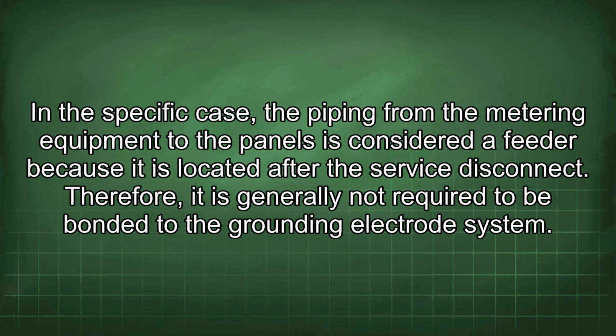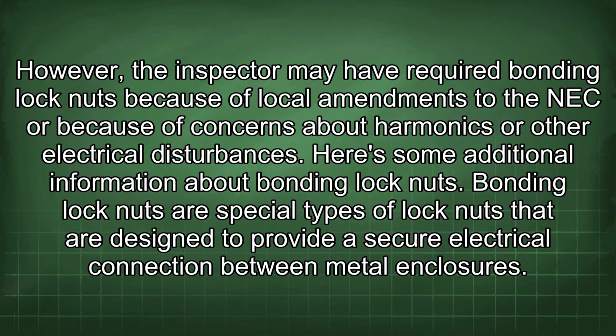In this specific case, the piping from the metering equipment to the panels is considered a feeder because it is located after the service disconnect. Therefore, it is generally not required to be bonded to the grounding electrode system. However, the inspector may have required bonding lock nuts because of local amendments to the NEC or because of concerns about harmonics or other electrical disturbances.